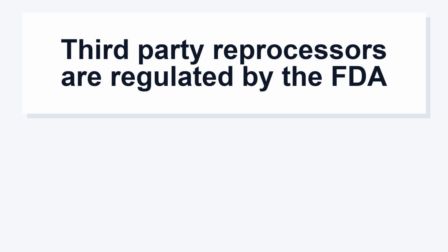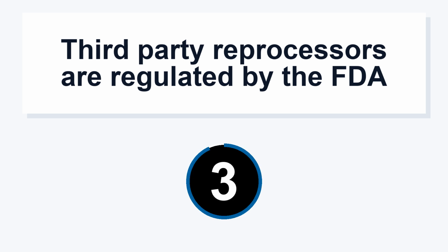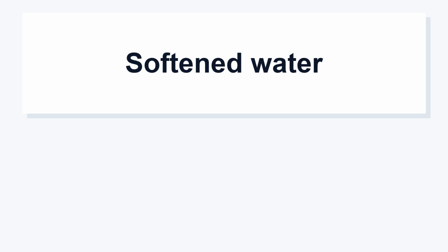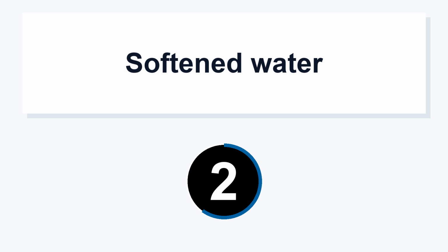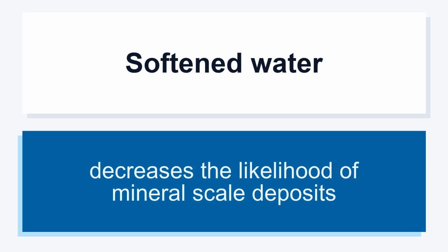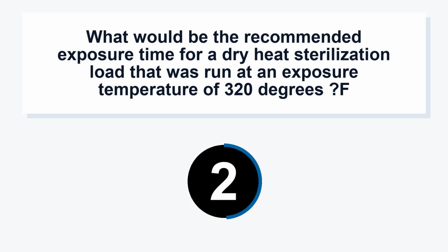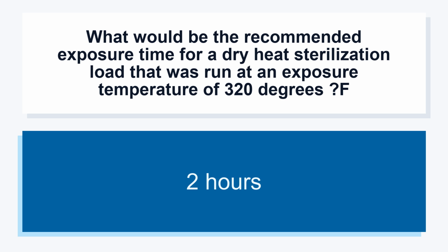Third-party reprocessors are regulated by the FDA. True. Softened water decreases the likelihood of mineral scale deposits. What would be the recommended exposure time for a dry heat sterilization load that was run at an exposure temperature of 320 degrees F? 2 hours.